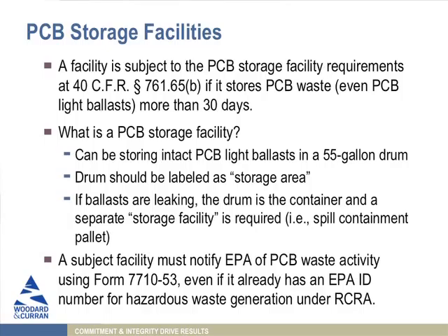The requirements of a storage area are that you have a 6-inch berm creating a containment area, big enough to hold the amount of PCB fluid that might leak out - twice as much as the single largest PCB item stored there, or a quarter of the total volume of all the PCB items that might be stored there. You basically need enough containment to make sure nothing's going to migrate. The floor needs to be smooth, preferably concrete or another non-porous material, and protected from the rain - so preferably with walls and a roof - to make sure nothing can migrate in the event of a leak.